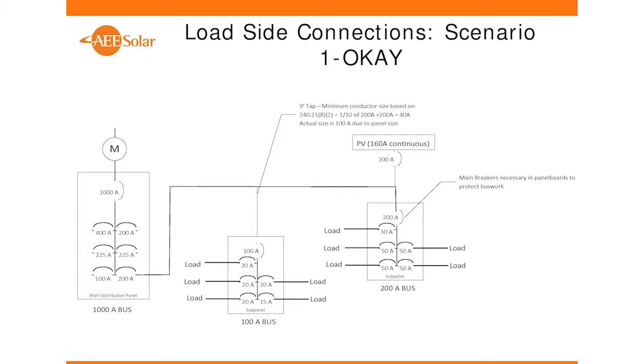And then we look, oh, I've got a 100 amp panel there. So the minimum is the greater of the two, whatever the load is, or 1/10 of the feeder breaker size. So clearly the 100 amp load overrules that. Now when you bring PV into it, it's like having a 400 amp breaker here, 200 plus 200. 1/10 of 400 is what? 40 amps. And then it would be the larger of the load or 40 amps, which it already is at 100 amps. And so you're good to go. So your short tap conductors are nothing to worry about. There's no way that a PV system is going to interrupt that issue.